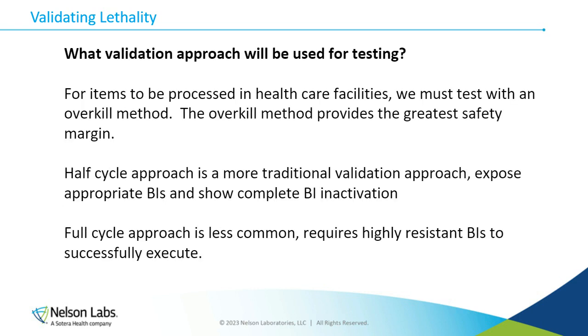When selecting the validation approach, I tend to prefer the half-cycle approach — it's more traditional and understood by more folks in the industry. However, depending on the resistance of the BIs available for testing, you may find your BIs are very highly resistant and the full-cycle approach might be a better option. As stated, it's much less common in the industry and tends to be applied better when validating industrial processes.